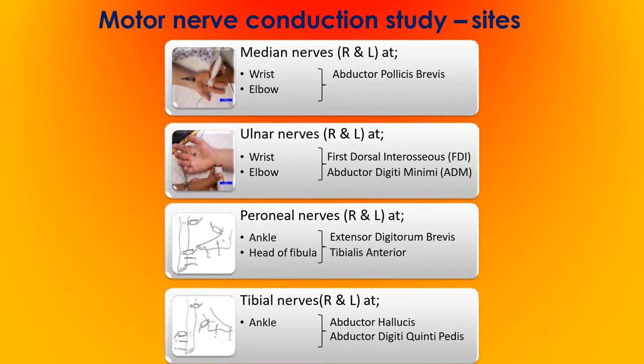The sites for motor nerve conduction studies are: the median nerve of the right and left arm at the wrist and elbow — the muscle typically recorded is abductor pollicis brevis; the ulnar nerve of the right and left arm at the wrist and elbow — the muscles are first dorsal interossei and abductor digiti minimi; the peroneal nerve of the right and left leg at the ankle and the head of the fibula — the muscle is extensor digitorum brevis and tibialis anterior; and the tibial nerve of the right and left leg, stimulated at the ankle — with muscles abductor hallucis and abductor digiti quinti pedis.